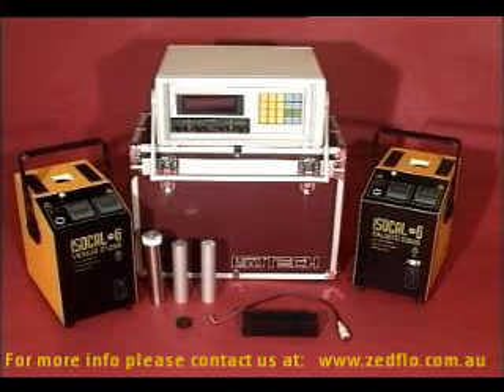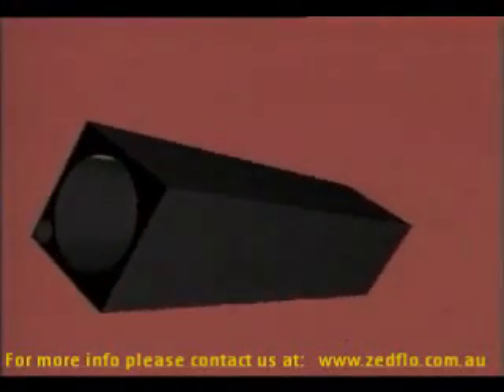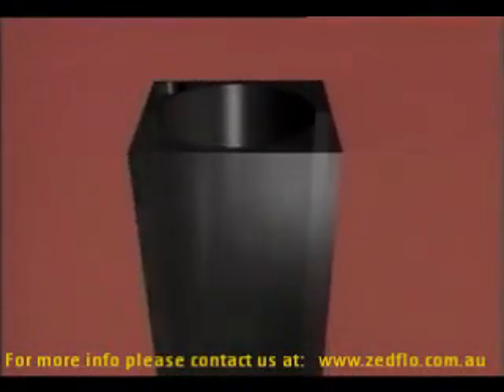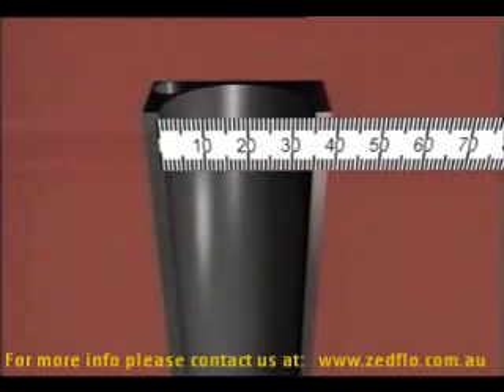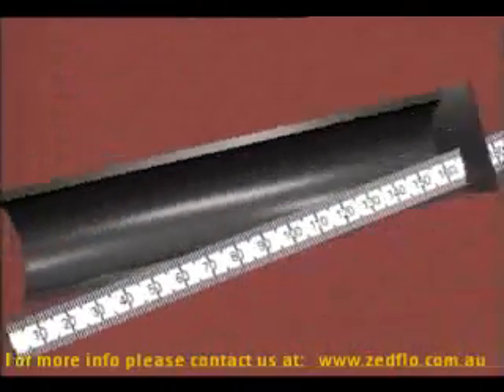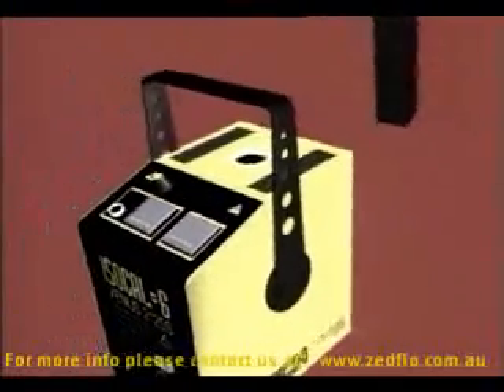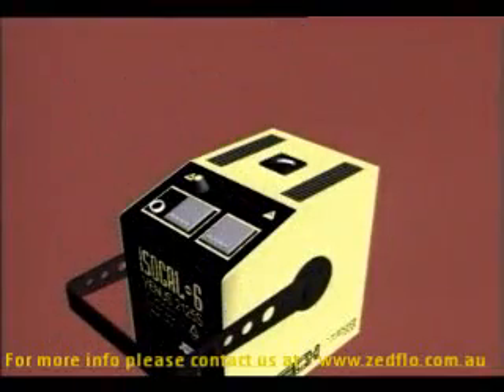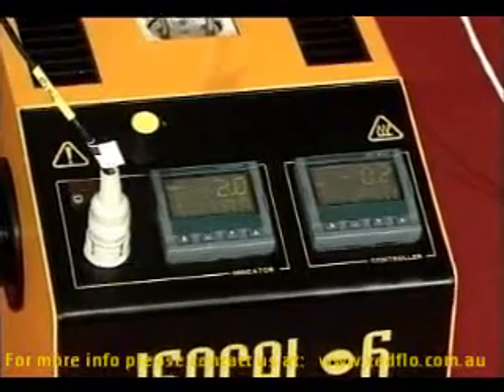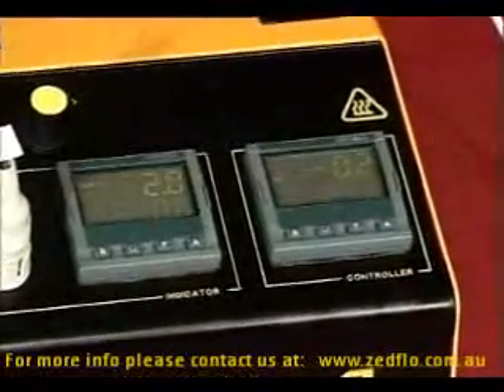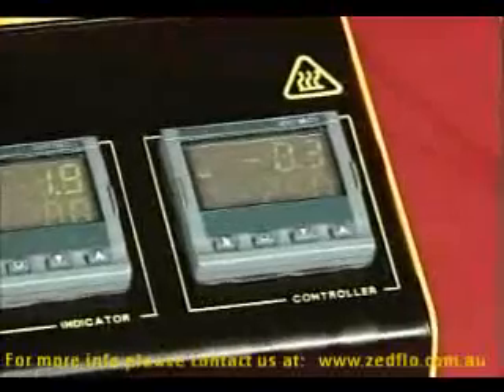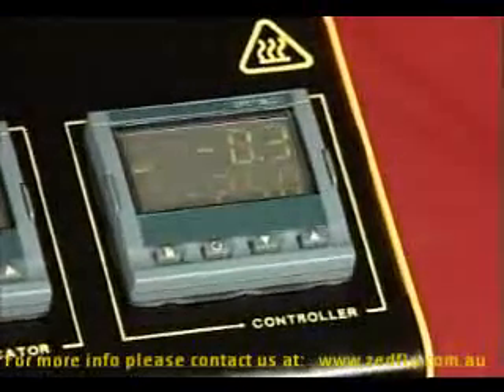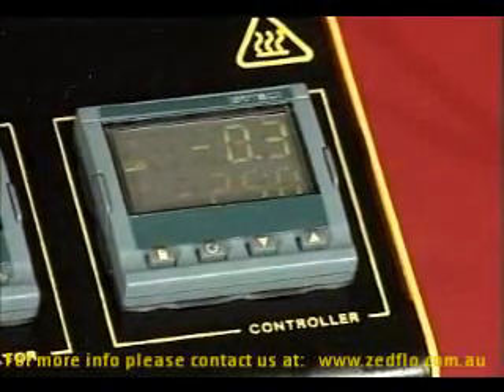So now let's take a closer look at the operation of the unit. The key to the Isocal 6 is the calibration volume shown here. It has an internal diameter of 35 millimeters and a depth of 160 millimeters. The calibration volume is heated in the Callisto, while it is either heated or cooled in the Venus models. A controller with a 0.1 degree resolution sets the temperature of the calibration volume. Our controller contains dedicated software that makes it more stable than other commercially available controllers.